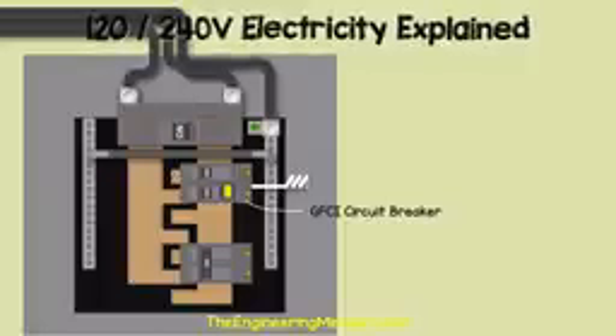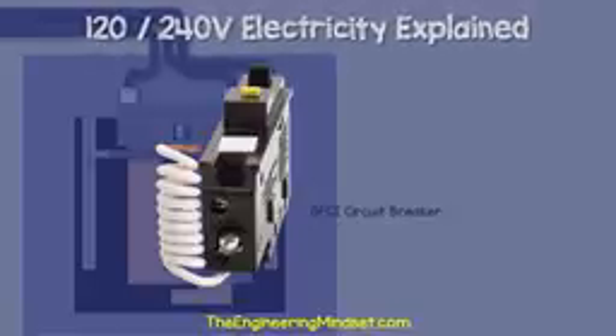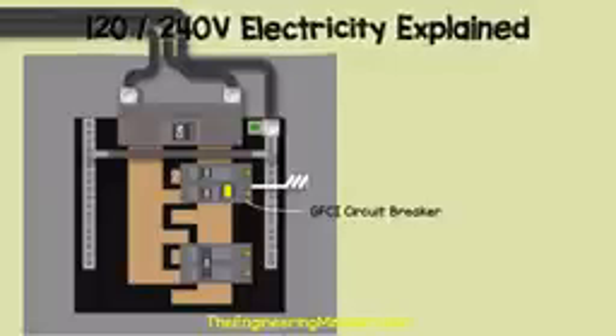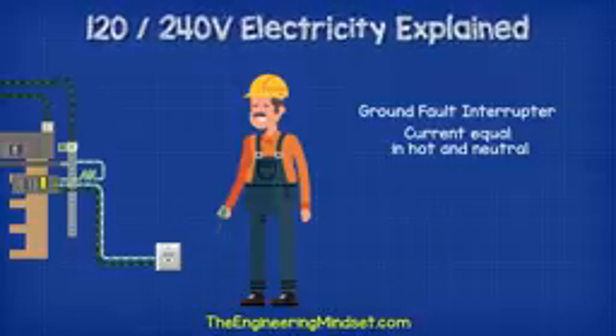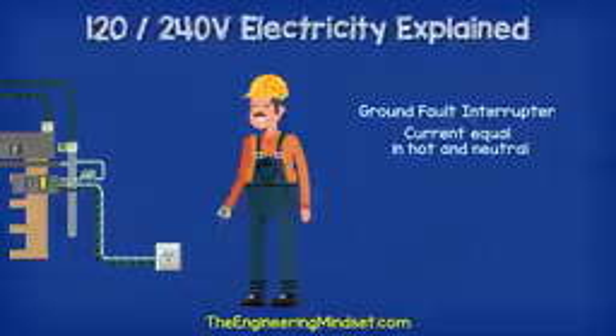We'll also very likely find a GFCI circuit breaker, which stands for Ground Fault Circuit Interrupter. This will look something like this, and depending on the model you buy, you will usually have a pigtail neutral wire connected to it. GFCIs are required on certain circuits where outlets are used for places like kitchens, bathrooms, hot tubs, etc. You should check with the National Electric Code for exact details. The GFCI breaker has both the hot and the neutral flowing through it. This way it can measure the current flowing through both wires and ensure they are equal.